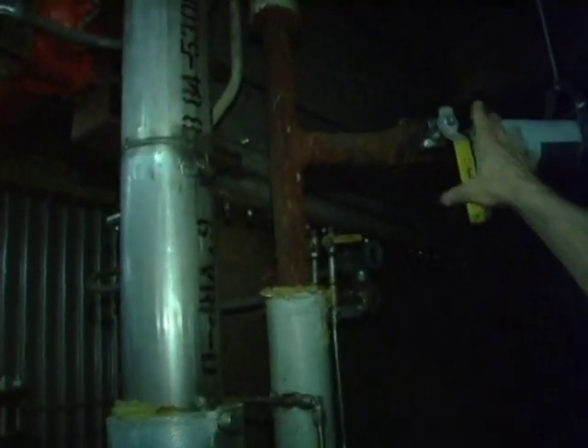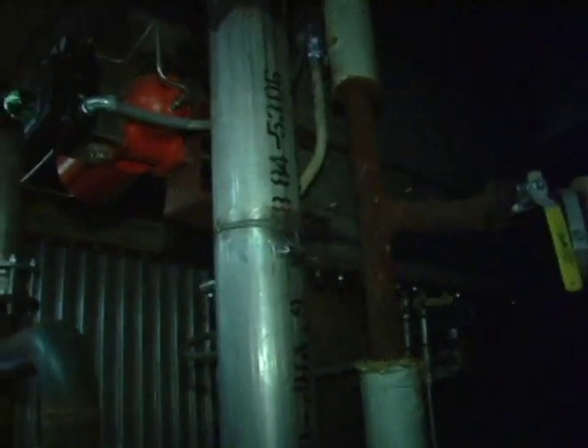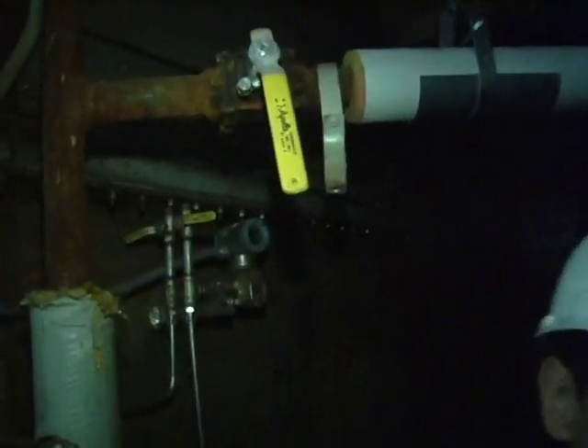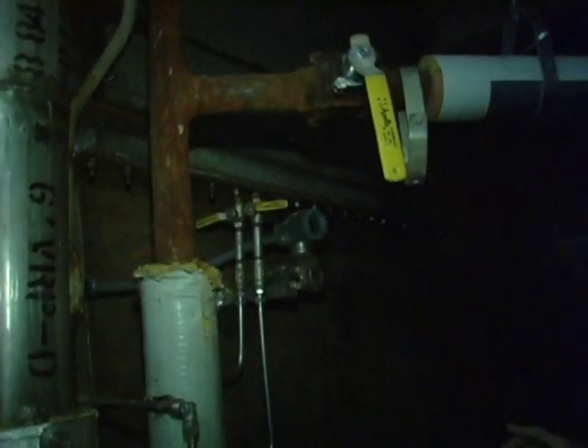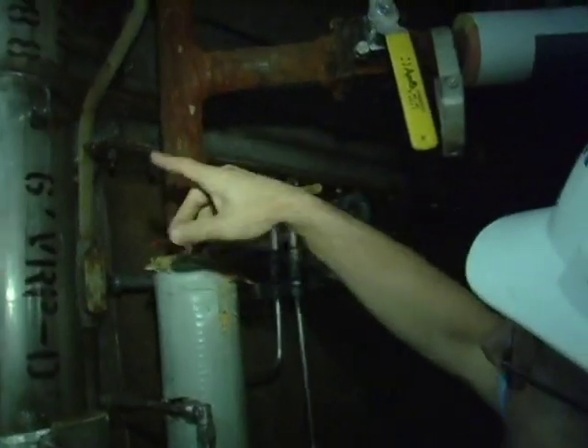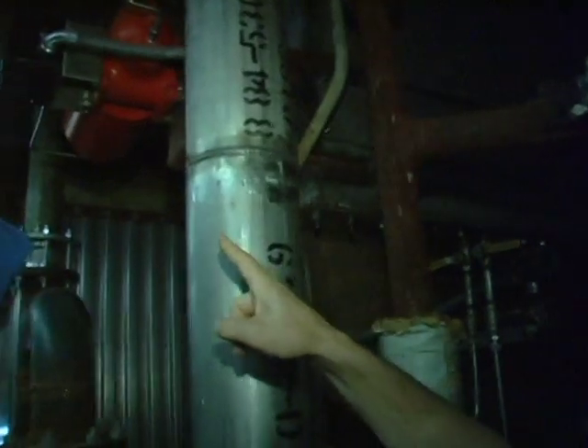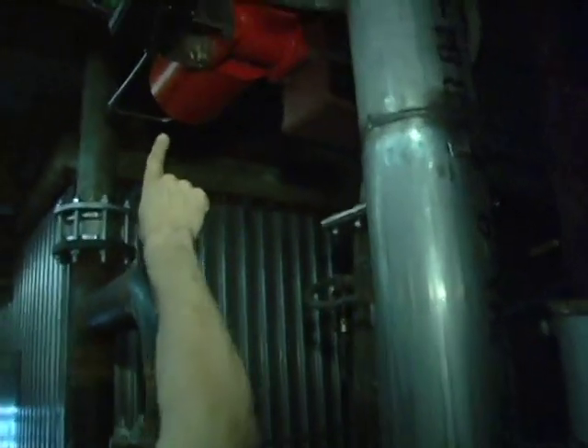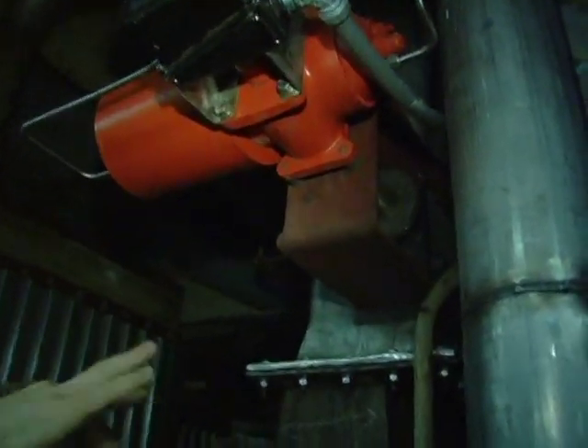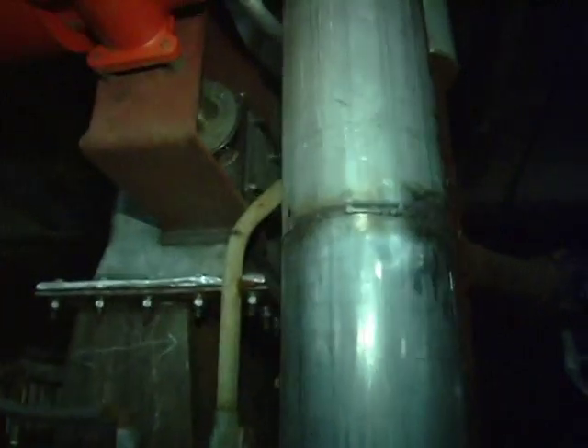Because this is the Venturi throat mechanism here. We replaced that whole damper section all the way from this flange to that flange, all new. And the actual damper mechanism is over here. It's this rod, this device right here. The shaft goes right through, and there's a damper in there which the shaft will turn.